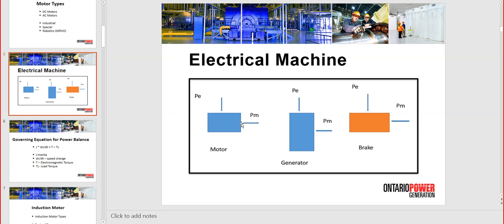In the case of a motor you want a low diameter, a longer body, in order to get the motor changing speed as fast as possible for different applications. And then the brake is when we command the electrical machine to go forward, reverse, but we stop at zero speed. So actually reverse two leads on the induction motor. The motor, if you leave it with the leads changed, will form a reverse rotating field and will go in reverse. But if you just want to stop, that is emergency stop, that is plugging. Reversing two phases will generate a reverse field, which the actual cage and the rotor will follow to a full stop. So you disconnect the power once the full stop is achieved.